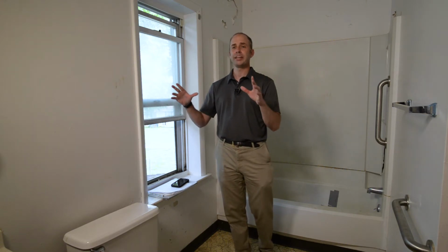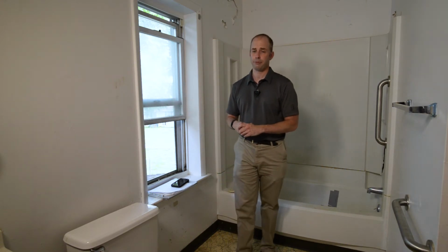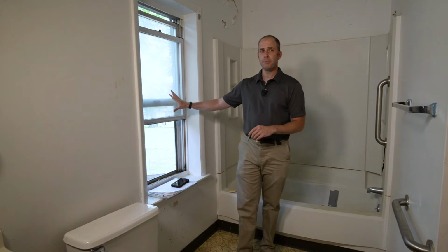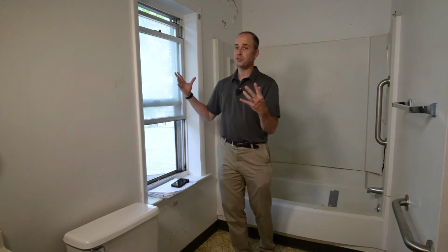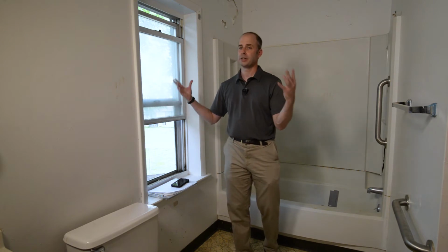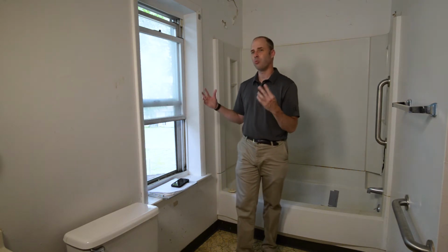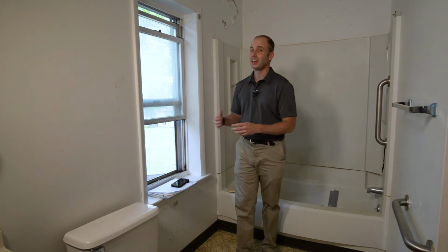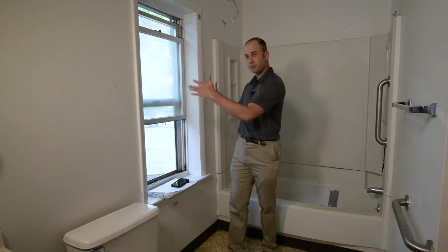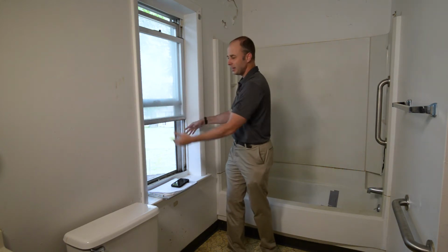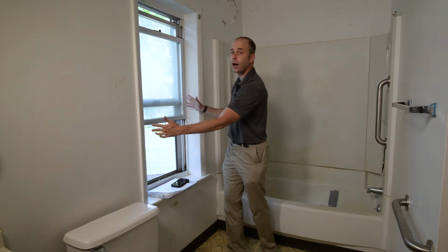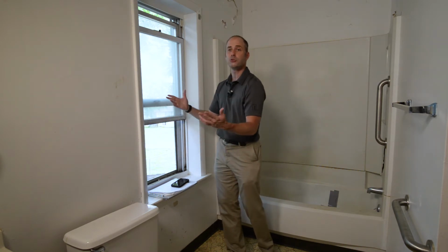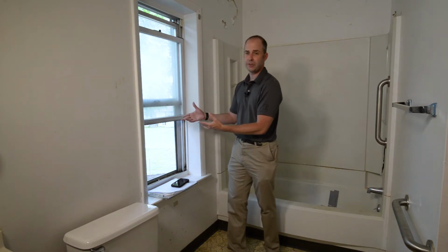Then also we're looking at the ventilation of a bathroom. So in here we have a window, and we will want to make sure that the window opens. How much does a window need to open in a bathroom, though? That's a common question that we might get, and it's 1.5 square feet that needs to open. So essentially, if a window is 2 foot wide, it needs to at least open 1 foot high. It's even less than that, because if it's 2 foot wide by 1 foot high, that would be 2 square feet. So we're looking for 1.5 square feet.